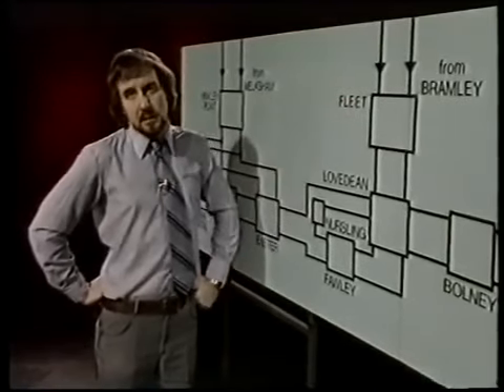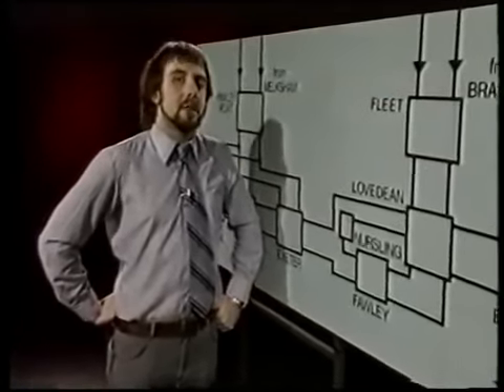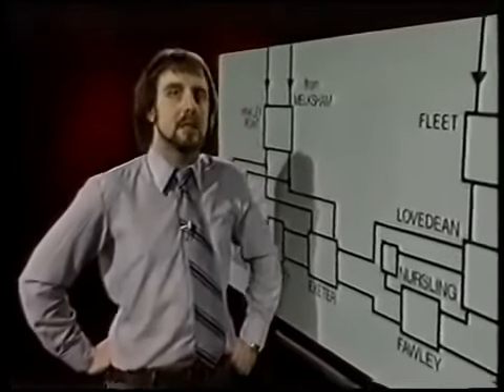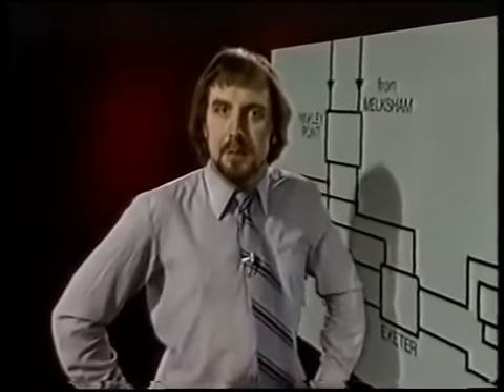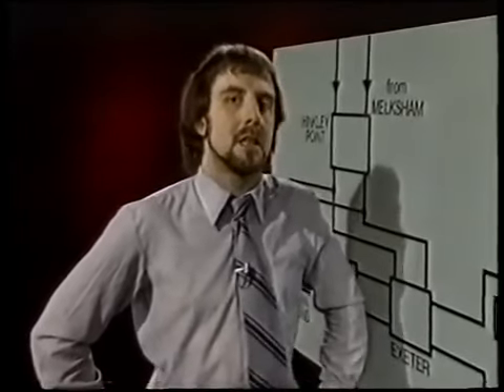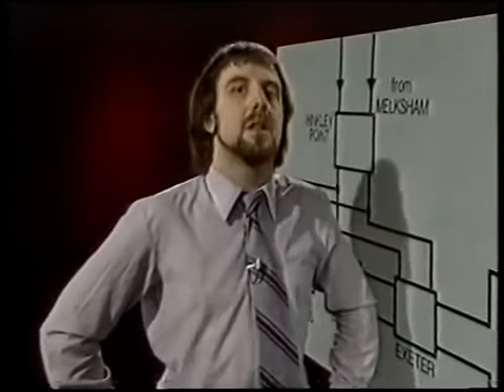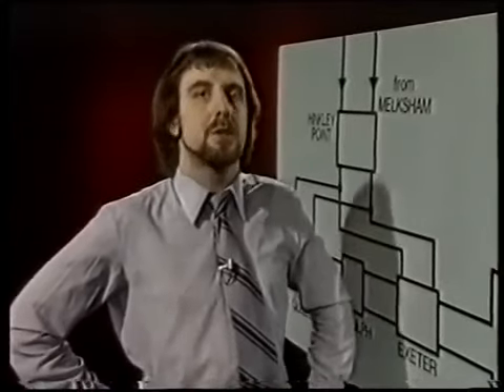A further possibility is to bring on new generating capacity as the proposed solution in the case of a line failure. In this case again, it must be anticipated some time in advance, because as we've said several times, the time needed to bring a boiler up to pressure and a turbine up to speed can be quite considerable.